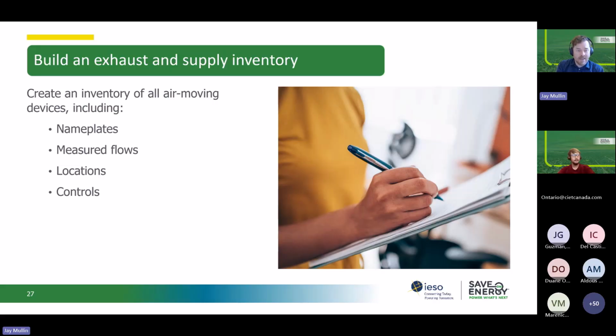On the exhaust side, obviously you're looking for those roof exhaust fans, process exhaust, dust collectors, fume hoods, paint booths, welding booths, washroom exhaust. But you also want to capture any oven, dryer, kiln, or other combustion related exhaust. Within that equipment, they're going to have some exhaust to expel the combustion products, so you want to make sure that's being captured in that inventory as well. Also, any always-on general exhaust that is often overlooked or people forget about in facilities. Sometimes there's just always an exhaust fan running in certain areas.